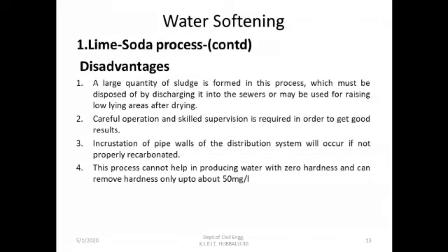Disadvantages are a large quantity of sludge is being formed. This is one of the significant disadvantages, wherein it has to be disposed of. Either it has to be discharged into sewers, or it may be used for raising the low-lying areas. Disposing of sludge is a big headache here. And then careful operation and skilled supervision is required in order to get good results. That is, what quantity of lime and soda has to be added, etc., has to be carefully operated or supervised.